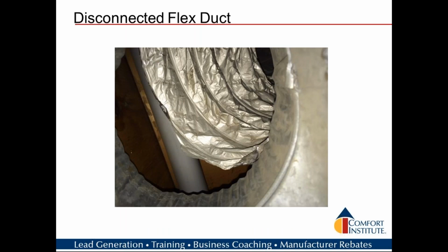Now, another technician in the company sent me the same picture. He pulled down a register when he was out doing a maintenance call. He looked up inside and found that the ductwork had actually been disconnected. This is in between floors, so he wasn't able to go on top and notice it, but he took the time to pull down a few registers to see what was going on.